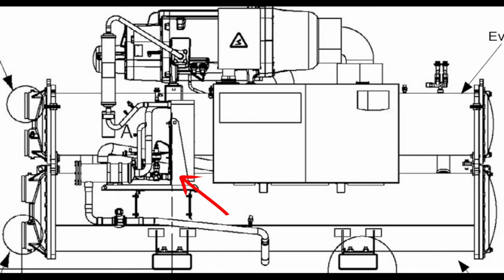We cycle through the brazed plate and we come out on the back side, but not this upright EXV, but there's another one back here that we could see from the other side or the other angle, that's coming out that pipe through that EXV and then out this insulated line into the evaporator. So that's the basic refrigerant circuit.